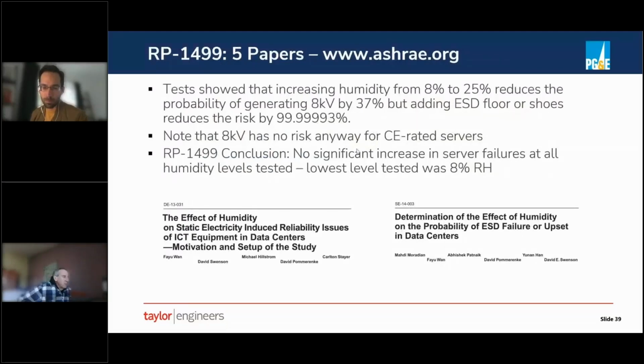ASHRAE actually did some research on this subject a few years ago, and they said the testing that they did showed that increasing humidity from 8% to 25% reduces the probability of generating a certain amount of charge from a person by 37%, but that adding ESD floors or shoes reduces the risk by basically 100%. And that even that 8 kV charge that person could generate was not a risk because the CE rated servers were able to withstand that level of charge anyway. We think again that the ASHRAE TC is doing a disservice by setting a humidity requirement that isn't justified by the research and the data that's out there. And one of the reasons why a lot of the clients we work with don't have a lower humidity requirement for their data center.